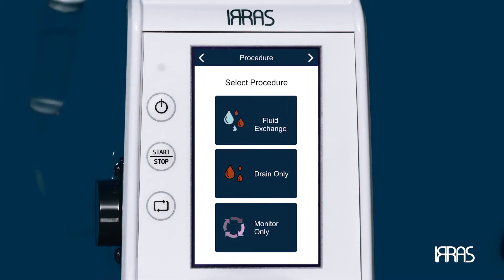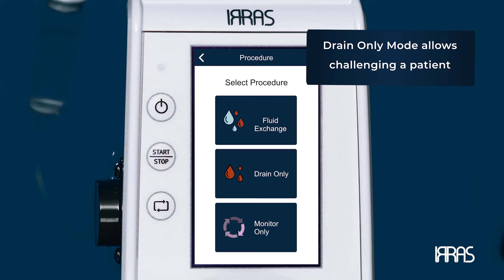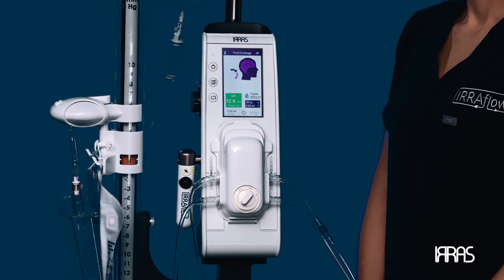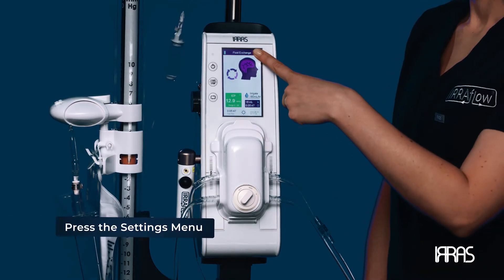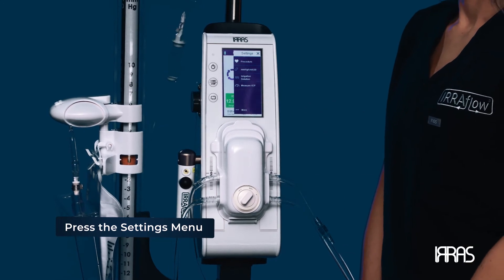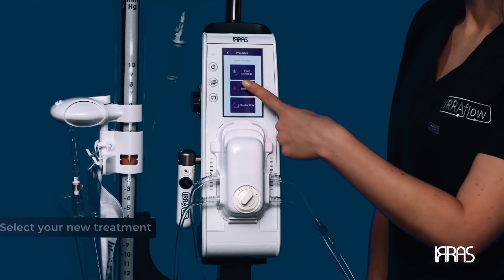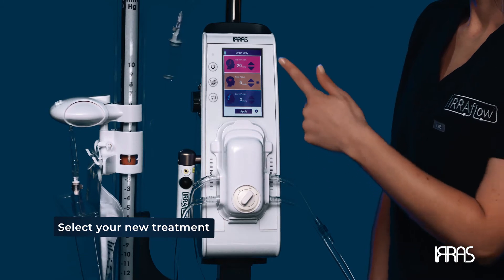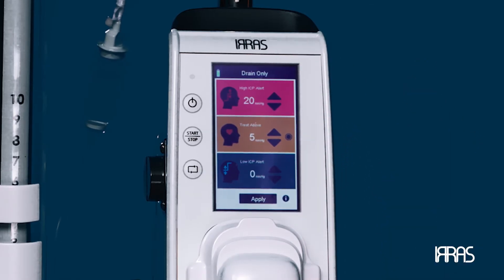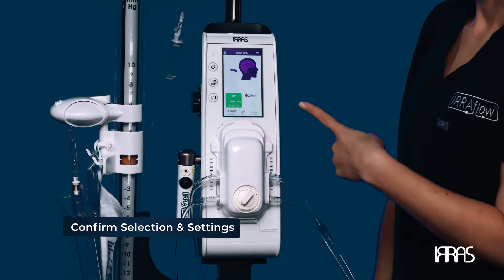Changing Therapy. During the course of treatment, based on the patient's evolving condition, the treatment option may need to be changed. The control unit can be placed into a drain-only mode or a monitor-only mode. This will allow you to challenge a patient at the end of treatment or operate the system without any irrigation. To place the control unit into drain-only or monitor-only mode, press the Settings menu on the touch screen and select the Procedure option. Based on your physician orders, select your new treatment. Confirm that you have selected the correct treatment and settings per physician orders and press the Apply button on the screen.